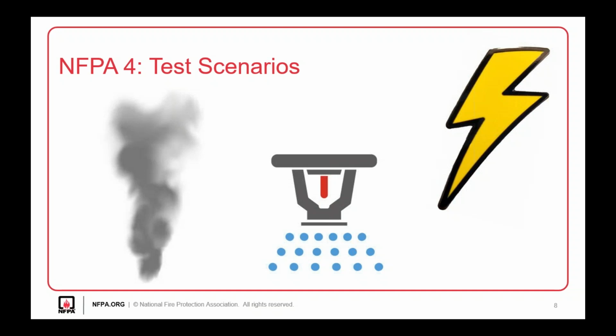Again, people assume that when they walk into a building, all the systems have been tested. They might have been through acceptance testing, but not holistically. That assumption alone is very scary. So it's important to develop a test plan or test scenario with teeth, and it's going to be different for each building. But NFPA 4 requires one or a combination of these scenarios to occur as part of the test.